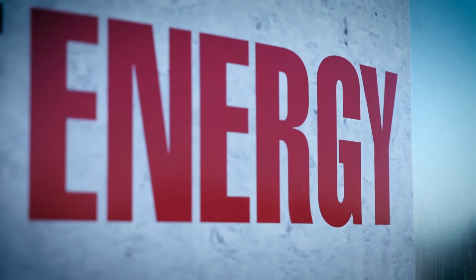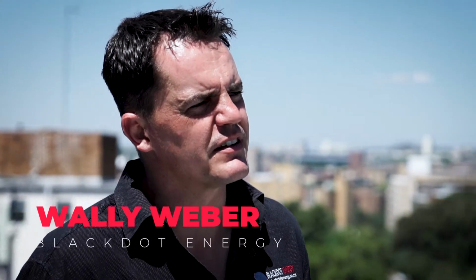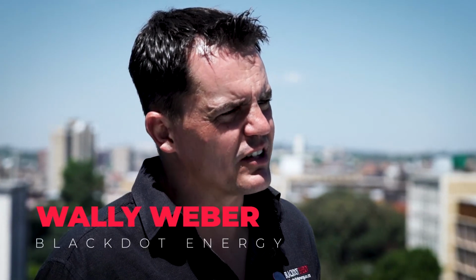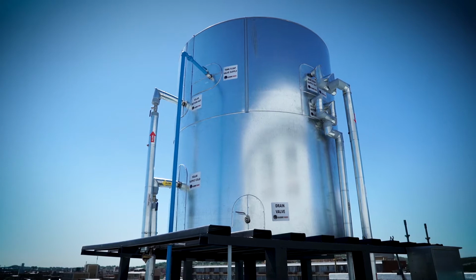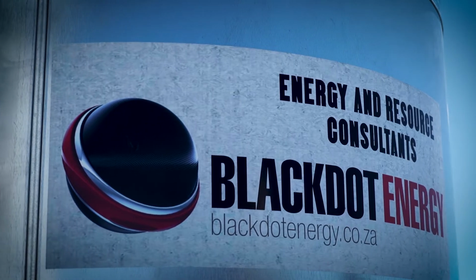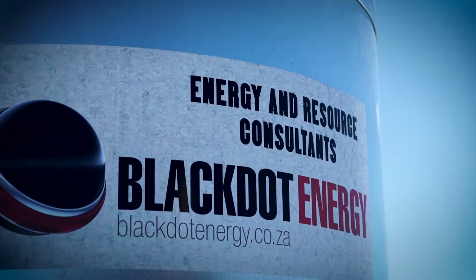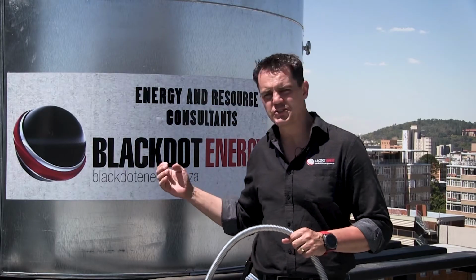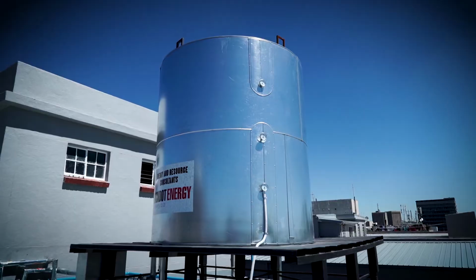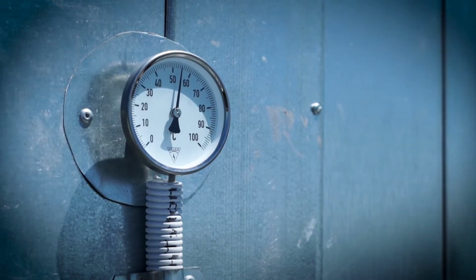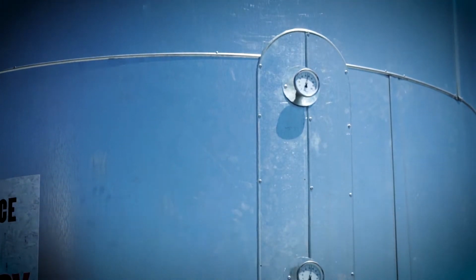Black Dot Energy consults for Energyweb in the design of the internal heat exchanger, which is a flexible stainless steel pipe. The internal heat exchanger gives you the benefit of both worlds: low pressure storage with a tank that can't rust, corrode, or burst, combined with a high pressure supply. That enables us to get an exact heat transfer of thermal energy from the low pressure liquid in the tank to the high pressure liquid that flows in the heat exchanger.